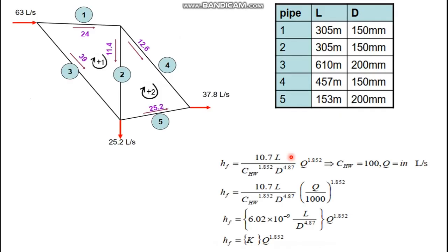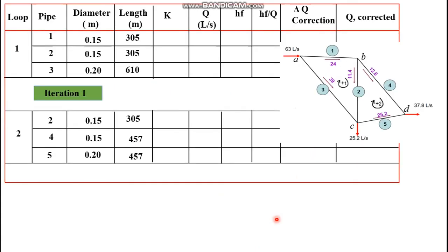So let's try to solve this problem. The first step is to calculate the head loss due to friction using the Williams-Hazen equation. We are given a Hazen-Williams constant of 100. We calculate the factor K by substituting the length and diameter for each pipe. K is given by the expression 6.02 × 10⁻⁹ multiplied by the length divided by the diameter raised to the corresponding power.